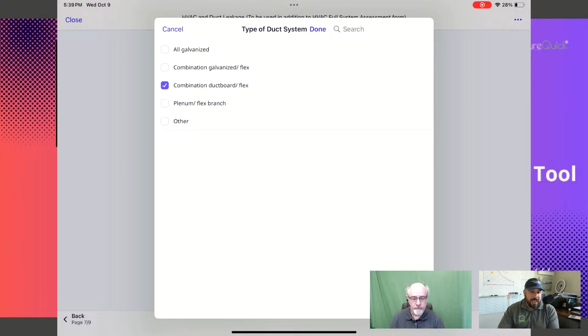Thank you. So let's just clarify for the listener. When you do a blower door test and you have your ducts open, not closed off like Tim had said here, then you can use a little pan that you put over the registers, and any leakage from outside that's coming in gives me some pressure on this pan that I can use to determine at a certain number, oh, that's where my dominant leakage is in that system. You can isolate where your duct leakage is with a blower door and a pressure pan. No duct tests are required. So the two together are very powerful, because I'm like, I have a lot of leakage, and it's actually these 3 runs that are giving me my greatest leakage. So there you go.